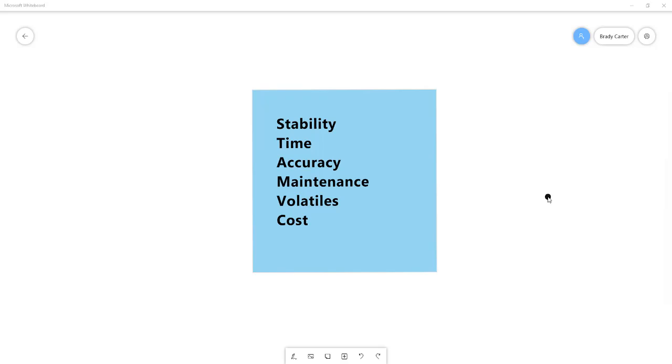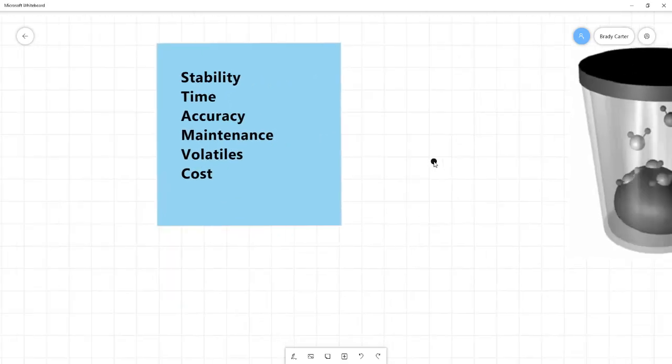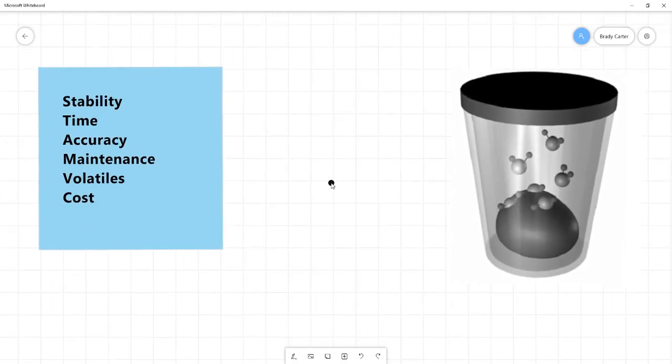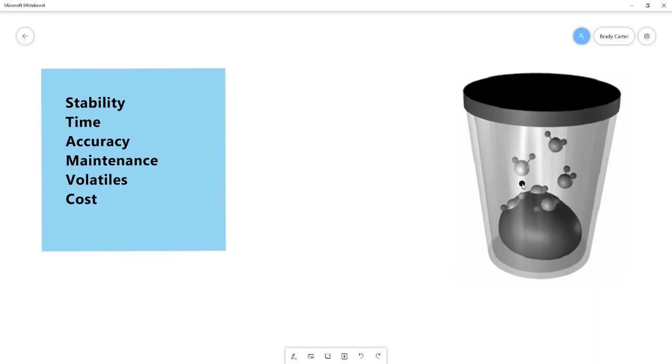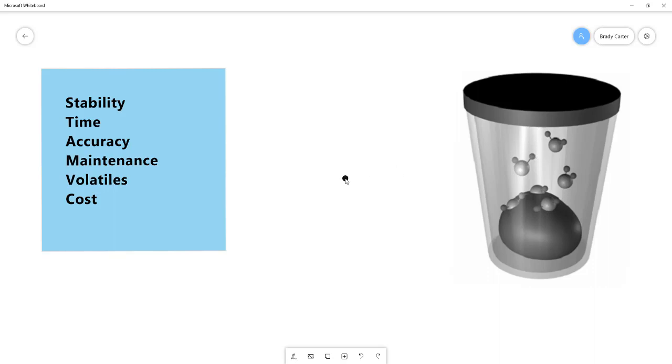And first, before we start our discussion, we need to highlight what a water activity measurement consists of. And the thing that's common among all water activity measurement methods is that a sample is placed inside of a sealed chamber, and then water escapes out of that sample. And over time, the headspace will come to equilibrium with the same water vapor pressure as in the sample. So that the relative humidity measured in this chamber called equilibrium relative humidity will be the same as the water activity of the sample. And the methods differ on how they actually measure that vapor pressure or that water relative humidity.